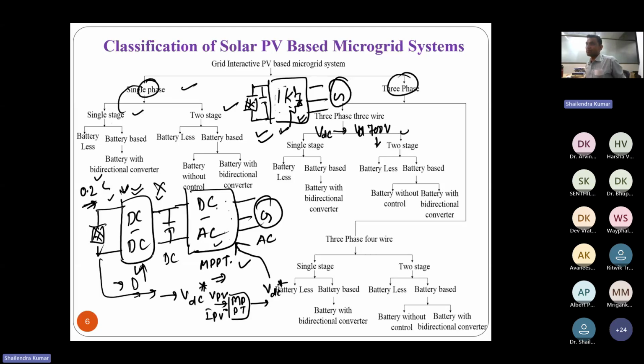We put a sufficient number of modules in series so that the duty cycle stays at 0.2 and not more, because putting modules in series decides the voltage. Suppose one panel has a voltage of about 32 volts, and I put 10 panels in series. What would be the voltage? 320 volts. So accordingly, I'll add panels to get the desired voltage.